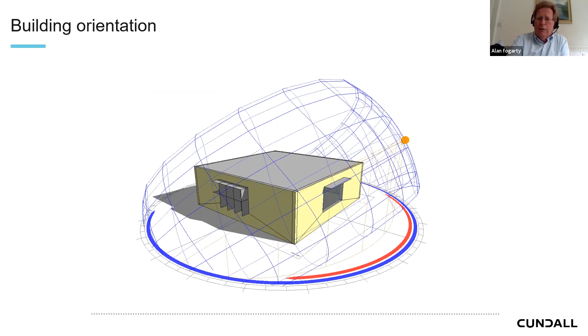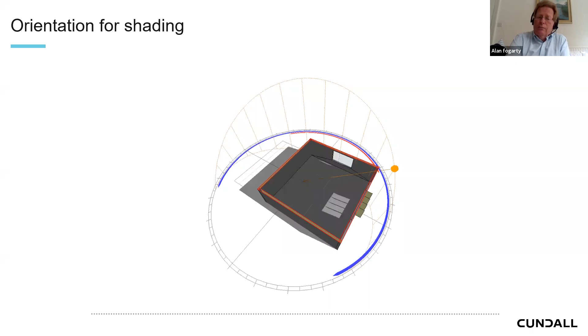So briefly looking at that, we can see a horizontal shade is very effective on a southern facade. If you put the same horizontal shade on a west facade, it's not nearly as effective. If you double it up, you get something quite useful. Looking at the equivalent area with a vertical shading system at peak time for an air-conditioned building, it does little or nothing in terms of protection. So preconceived ideas about shading and orientation really do need rethinking.